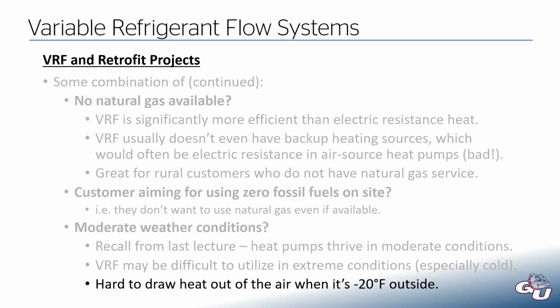You can also probably imagine if you're getting to minus 20 outside, you might be limited on how much of that energy sharing is going to go on. How many of your spaces in your building are actually going to be in cooling mode if it's that cold outside? You still might have a few, especially if they're internal rooms that don't have any exterior exposure. But at the end of the day, it might not be a good fit. So any one of these reasons, or usually multiple reasons, make VRF a system type that we would generally recommend.